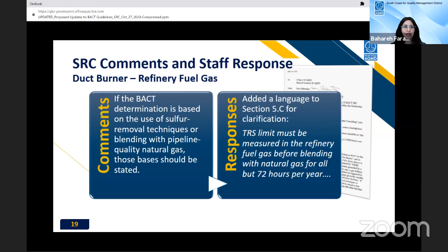And this is the last two comments. It was not clear if the limits were for sulfur as sulfur, sulfur as H2S, or sulfur as SO2 plus sulfuric acid. Since the duct burner exhaust gas is diluted with the exhaust from the gas turbine, the fuel directed to the duct burner must comply with the fuel gas H2S limits, because, as Dipankar also mentioned, there are two ways to measure sulfur: directly in the fuel gas, or measure SO2 after combustion and back calculate to total reduced sulfur.